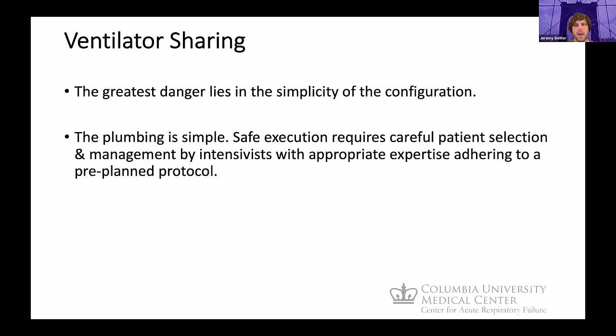So our protocol had some key safety measures I think is worth highlighting. One is the use of pressure control. The reason for that would be that mechanical changes in one patient would not affect the other, because you have two circuits in parallel. According to Ohm's law, the driving pressure would stay the same if something downstream changes in one patient. We both thought this theoretically, but also then tested it with test lungs to confirm that that was the case, that the ventilator would continue to function properly.